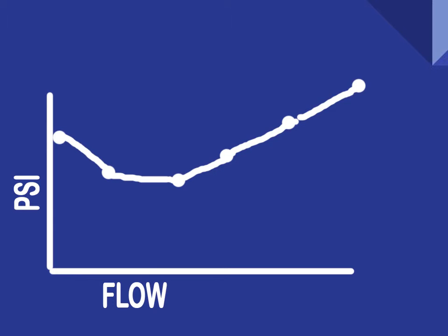This also applies to things with a negative loss, e.g. fire pumps. A pump's pressure boost changes depending on the flow, but a pump itself doesn't add flow. It simply increases downstream pressure dependent upon the flow. Since the pressure is vastly different at the pump suction and the pump discharge, a node should be associated with each. All these put together, and your system with nodes should look roughly like this example of a multi-story building with standpipe and pump.